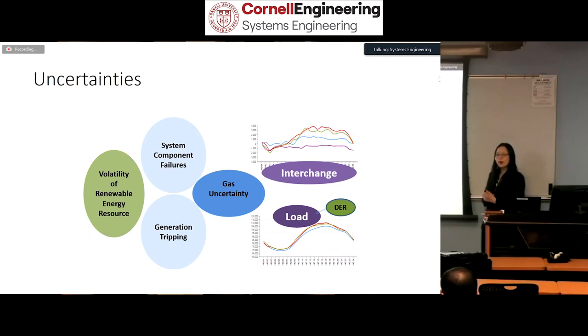This adds more variability and uncertainty to the load side, so that's a new problem. Then there's interchange—the activity between different markets and control areas—which can cause a big change, especially to the PJM system. Interchange can swing 7,000, even up to 10,000 megawatts, in just 10 minutes.